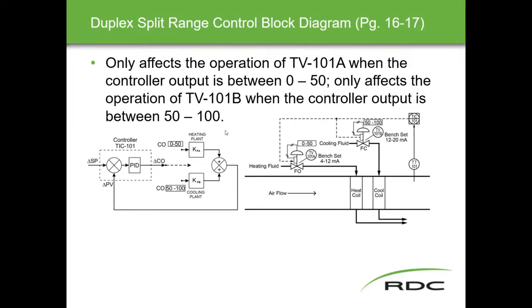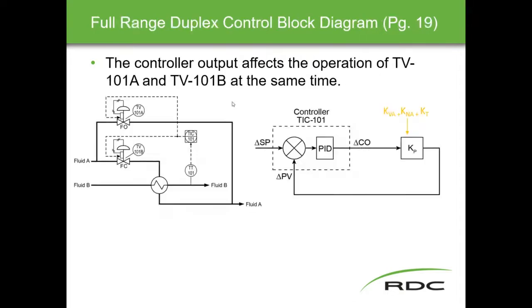For the full range duplex block diagram, it's slightly simpler: the controller affects the operation of both TV-101A and TV-101B simultaneously. You can see the signal coming out of the controller being split to both valves. The plant gain block combines valve gain, process gain, and transmitter gain into a single block. So: full range duplex gives essentially one transfer function, whereas split range duplex gives two transfer functions.